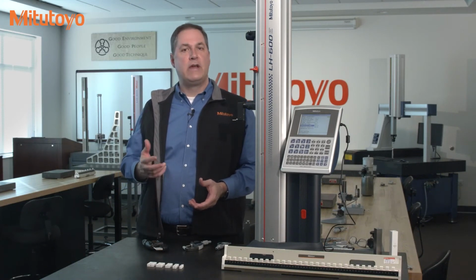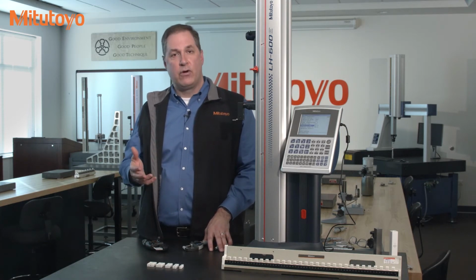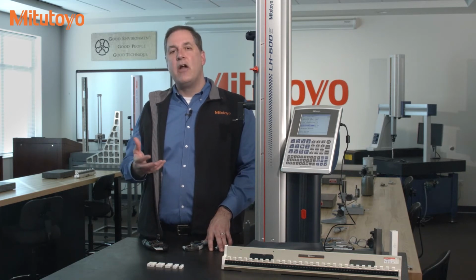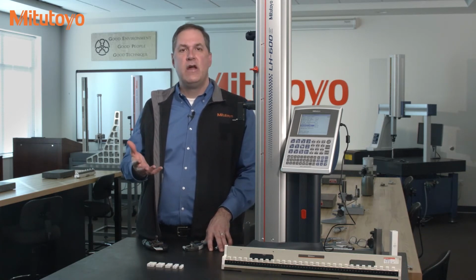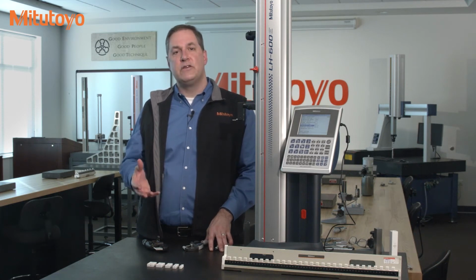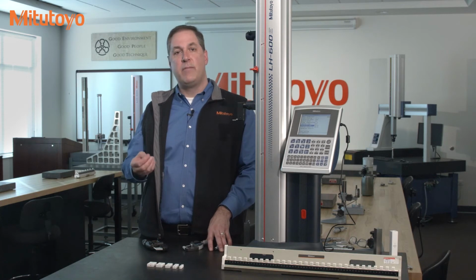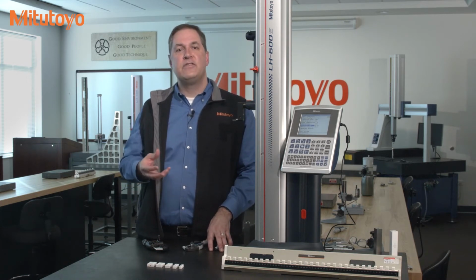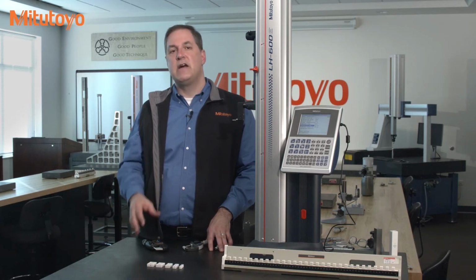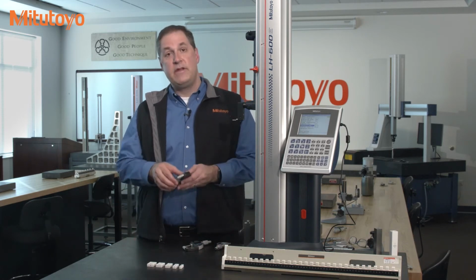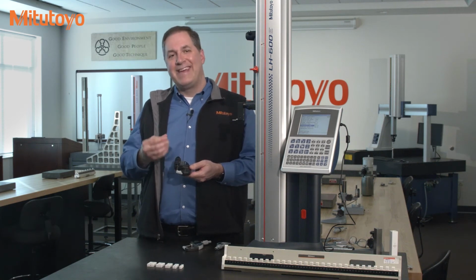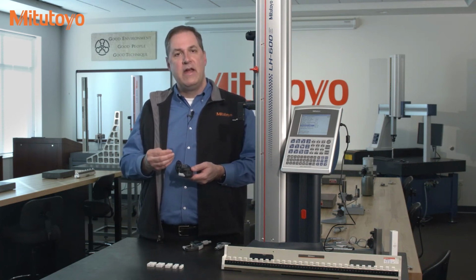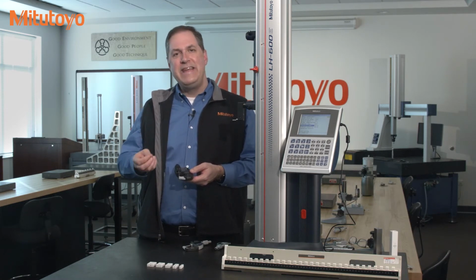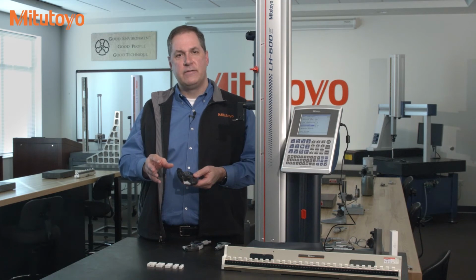In our micrometer episode, we recommended using grade 0 gauge blocks for calibrating micrometers. If you watched our episode on measurement quality requirements, where we discussed TAR and TUR, you learned the reason for using grade 0 gauge blocks when calibrating micrometers is to ensure sufficient calibration capability when checking the tolerance of the micrometer. For the MDH, being so much more accurate, the capability of our calibration method is no longer good enough. We need to change something with our reference standards.